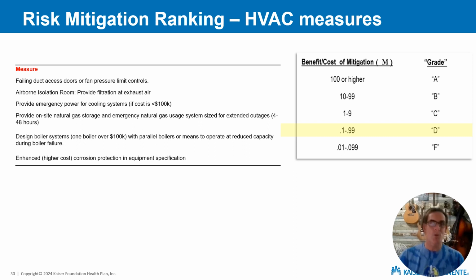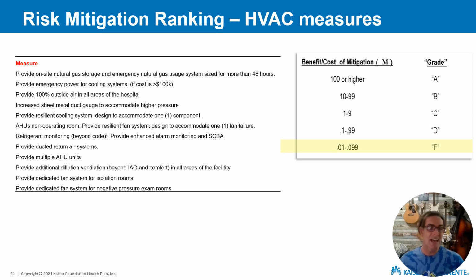Second from the bottom is where we see dual boilers that are more than $100,000. Still, this is not N+1. This is reduced capacity at equipment failure, and we're at a D level investment. And then finally, we get to the Fs. These are the list of investments where the level of investment required is 2 orders of magnitude higher than the potential benefit that you could get from it.